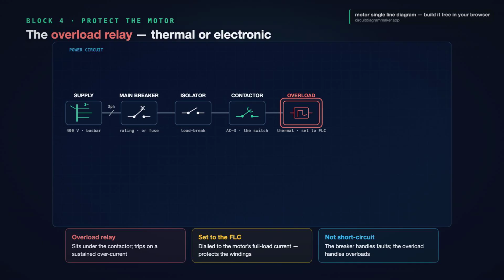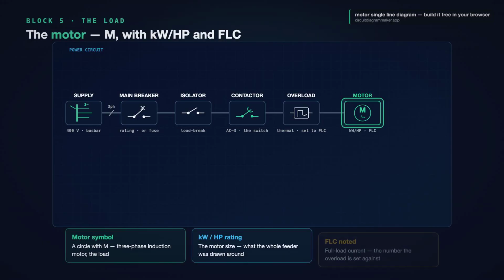Block 5, the motor, the load the whole drawing was built around. On the single line diagram, it is the classic symbol, a circle with a capital M inside, marked 3-phase. Simple to draw, but next to it you write the two numbers that define the entire feeder. The motor's rated power, its kilowatts or horsepower, because that is what sized the cable and the contactor in the first place. And its full load current, the FLC, the exact number you just dialed the overload to. Get the motor's kW and FLC on the page, and every device to the left of it suddenly has a reason for its rating.